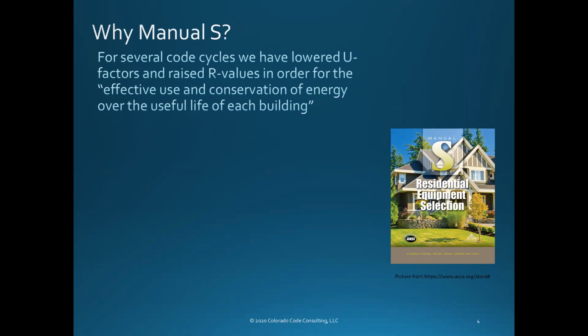Clearly never. So how do we save energy? Do we save energy by raising R values and lowering U values? No, the only reason we save energy is that we actually size the equipment correctly. That's it. Sure, we're going to have a wonderful building thermal envelope, it's awesome, and then we put the same size furnace and air conditioning in there we always have. What have we done? We haven't saved any energy at all.